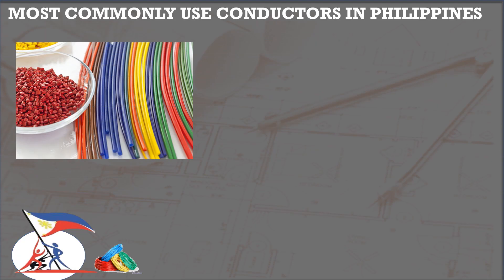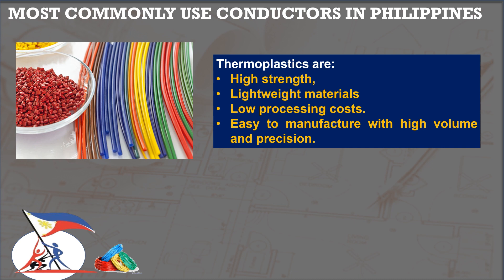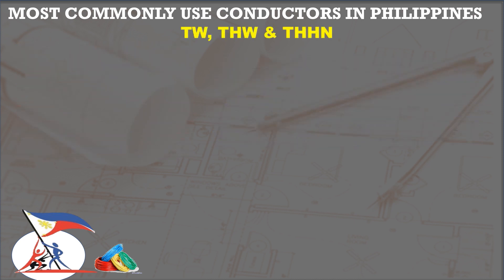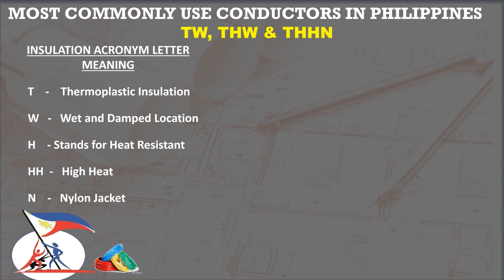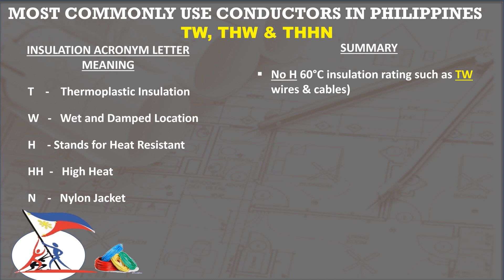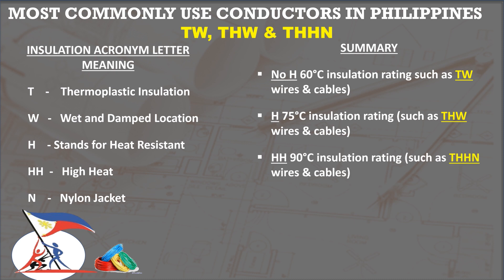In the Philippines, thermoplastic insulation is commonly used due to its high strength, lightweight material, and relatively low processing cost. These are TW, THW, and THHN, where T is for thermoplastic, W is for wet or damp location, H is for heat resistance, double H is for high heat, and N is nylon. If there is no H, such as TW, the temperature rating of insulation is 60 degrees Celsius, while HH has an insulation temperature of 90 degrees Celsius, and when an insulation has dash-2, this is also 90 degrees insulation.